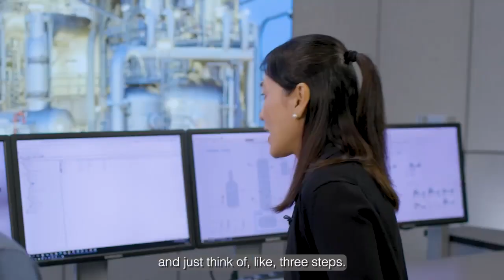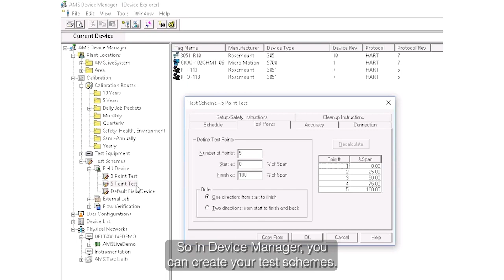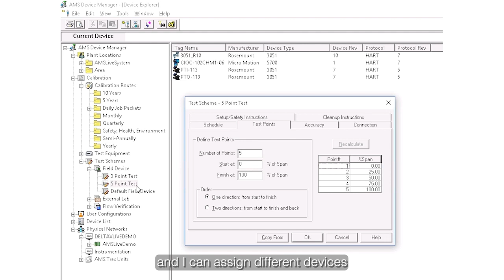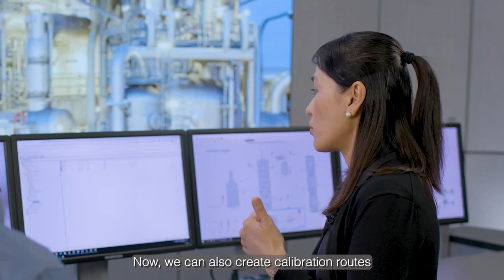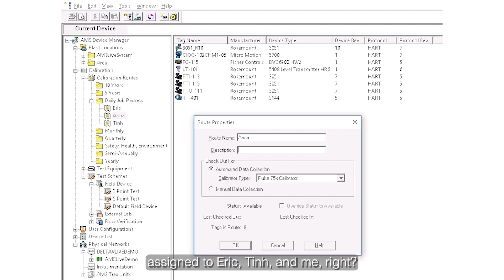Okay. So I'm going to go back to the device view screen here and just think of like 3 steps. One is, Tin was talking about having those 5-point tests. So in Device Manager, you can create your test schemes. So here I have a 5-point test scheme, and I can assign different devices that use that specific scheme, all right? Now, we can also create calibration routes for the different technicians that you have in the plant. So what I have here, I actually have some routes assigned to Eric, and Tin, and me, right?